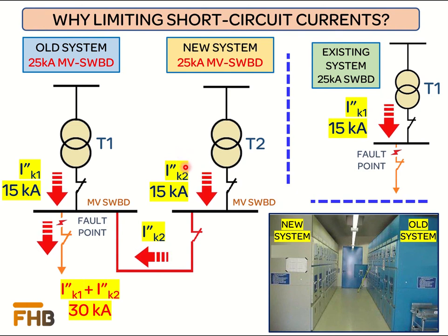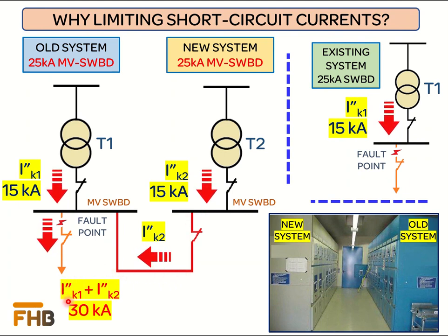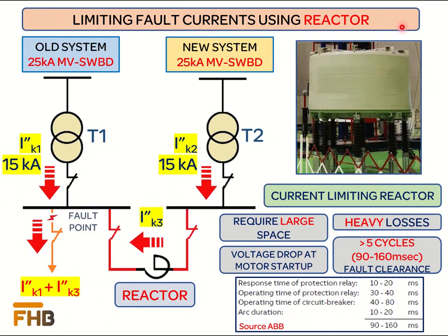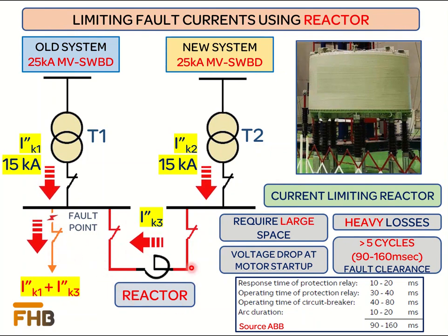The problem starts once we couple the two systems together through a bus coupler, as the combined short circuit of the two systems will be around 30 kA, which is more than the rated short circuit value of the switchgear. One option to reduce the short circuit current entering from one system to another is by increasing the inductance of the current path through the introduction of current limiting reactors.